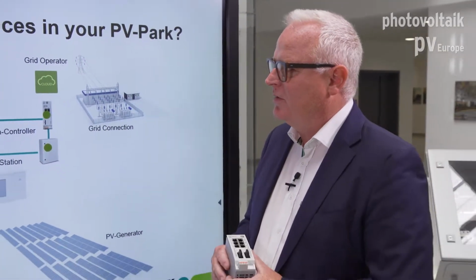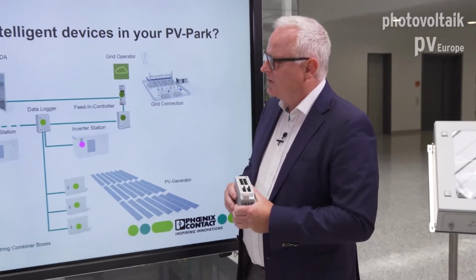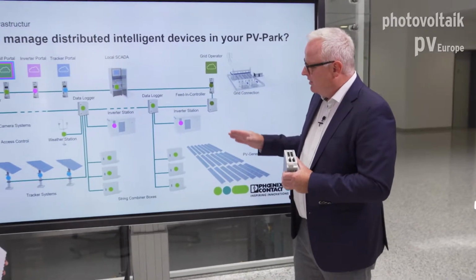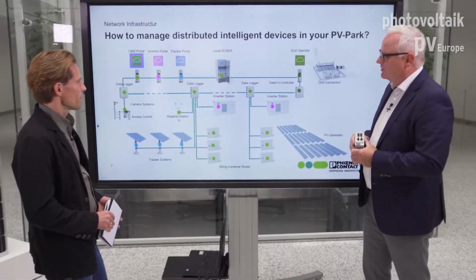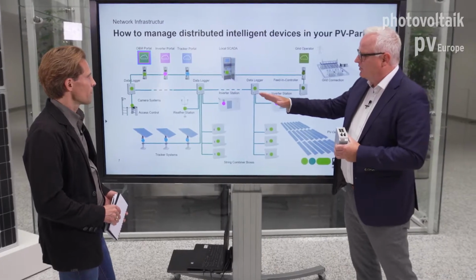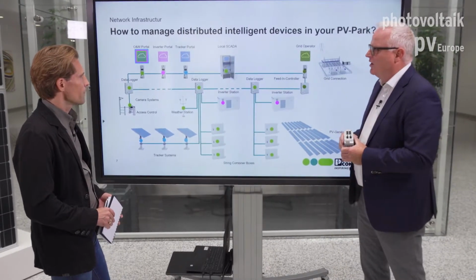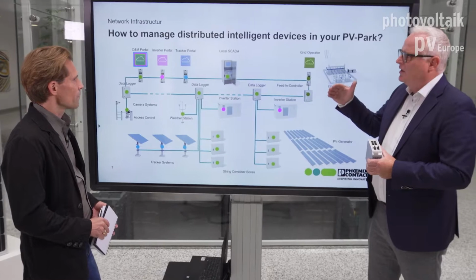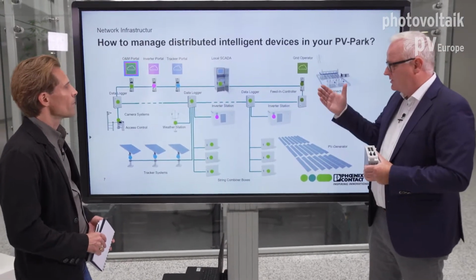What we show here is a complete topology of such a PV park system. You see all the network components. All these components generate data. Even if it's the string combiner boxes or the tracker systems or the weather station, inverter station and so on, also the camera systems, all these devices send data to the upper-leveled portals or the local SCADA system.